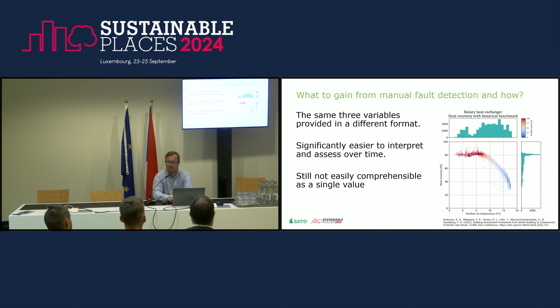This is very nice, but it won't give the operational personnel a single value that they can quickly use to operate. So we then progressed to try and combine all this data into a single KPI - the one you see here in blue. It's what we call, shortened as URED, which is Useful Heat Recovery Efficiency Deviation. What it simply means is that we assess how much heat recovery efficiency we actually have compared to what we could actually use.